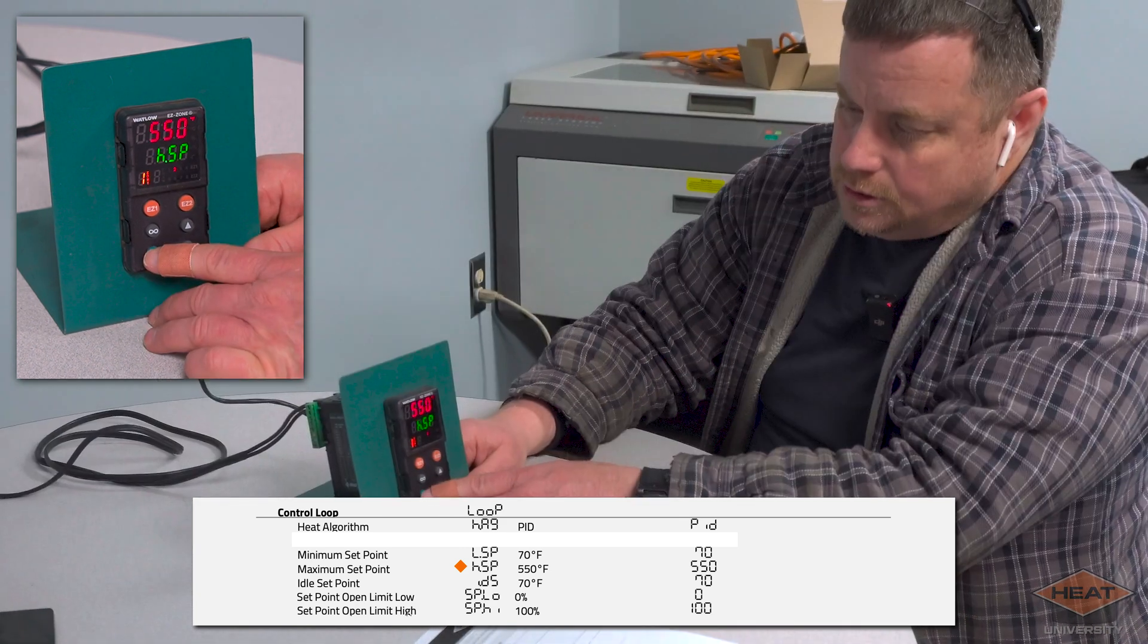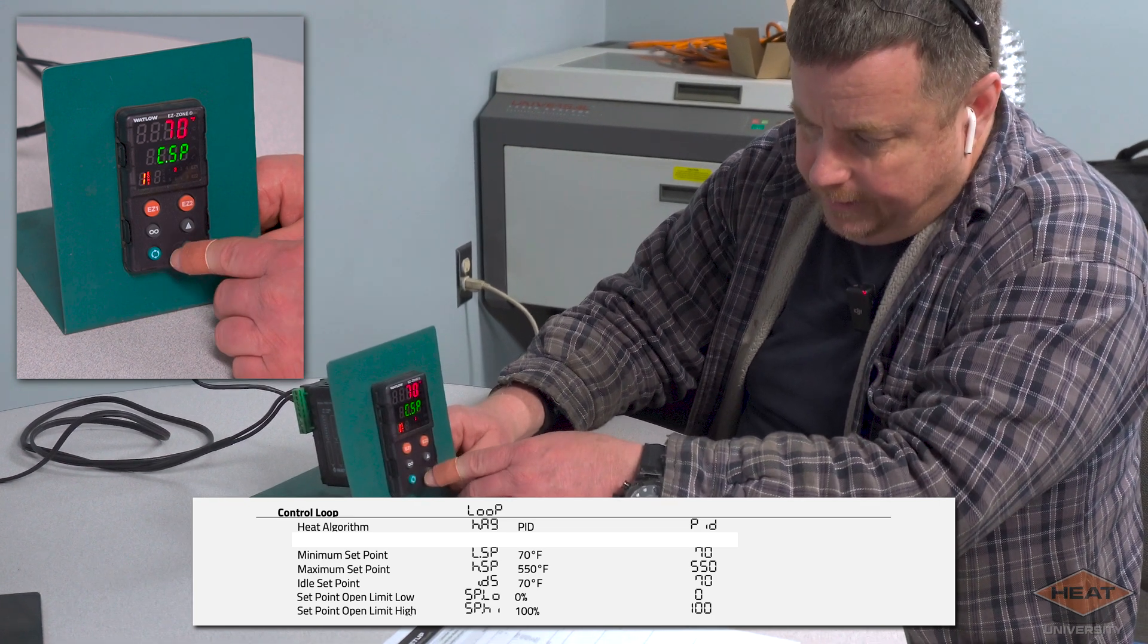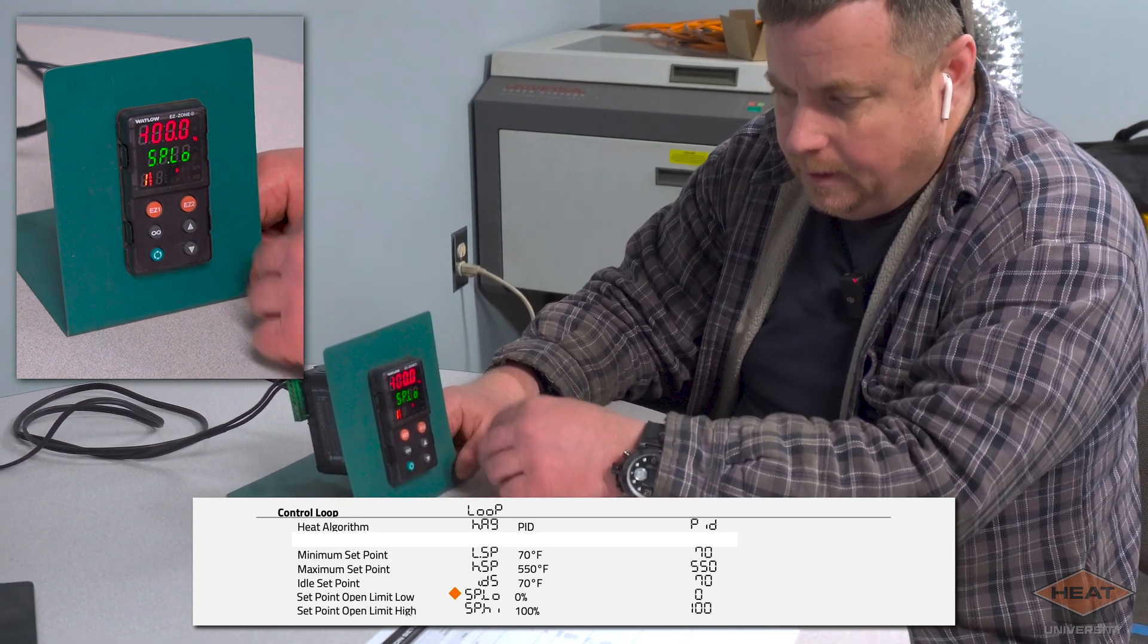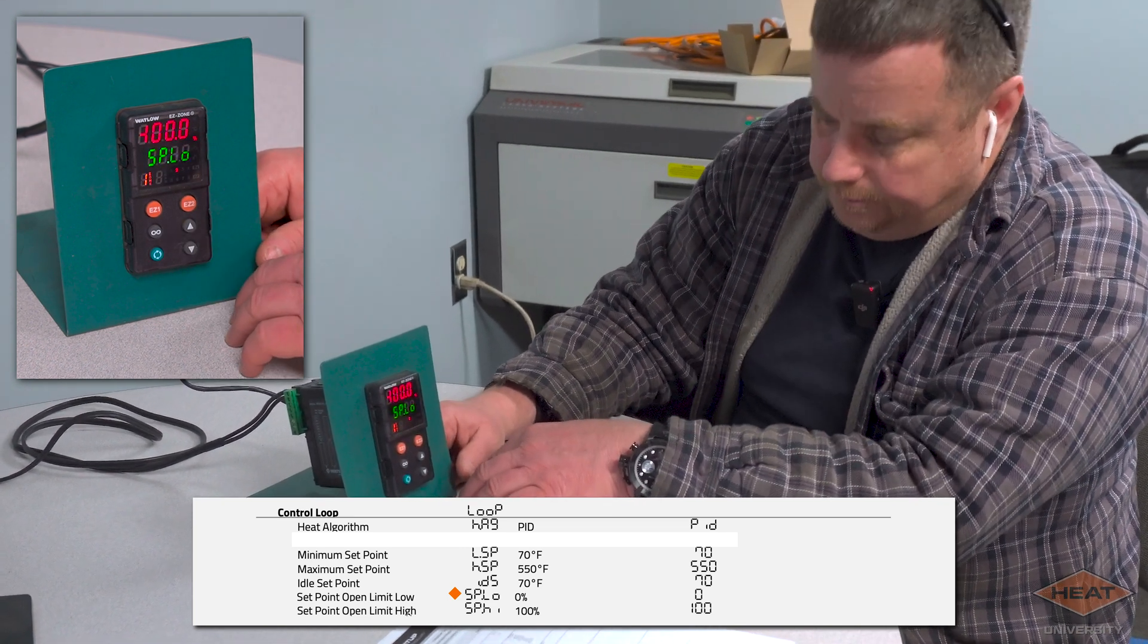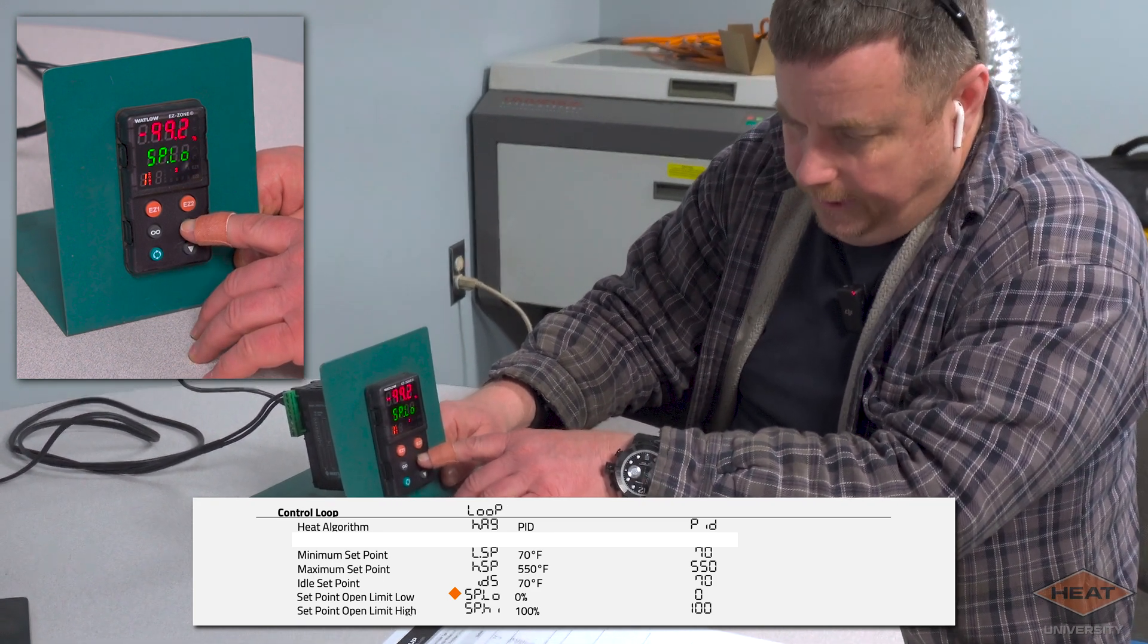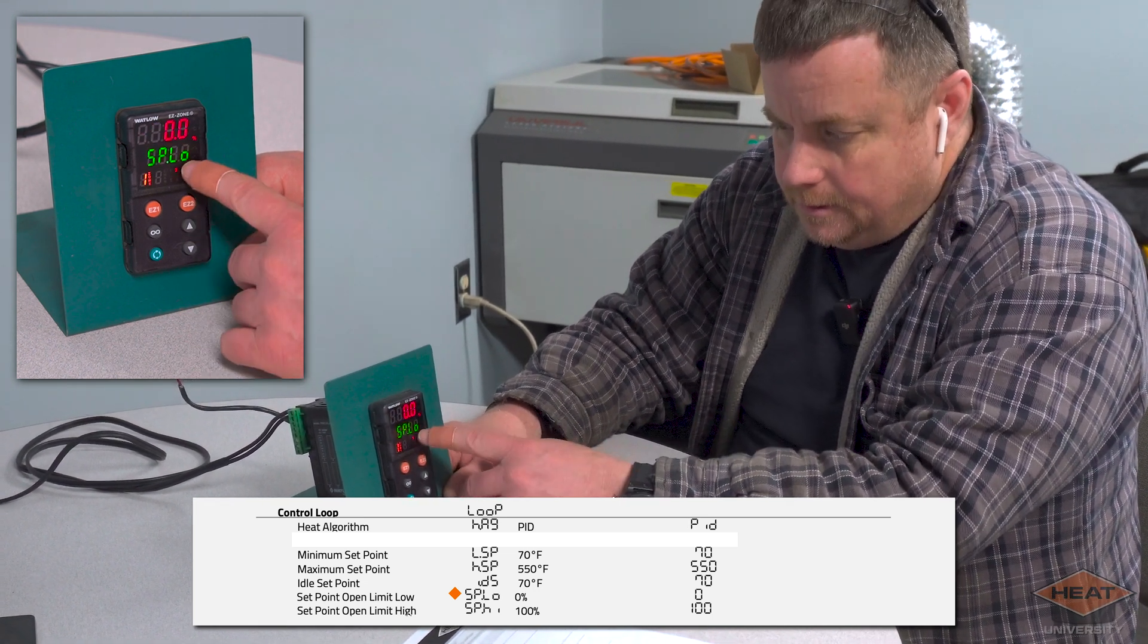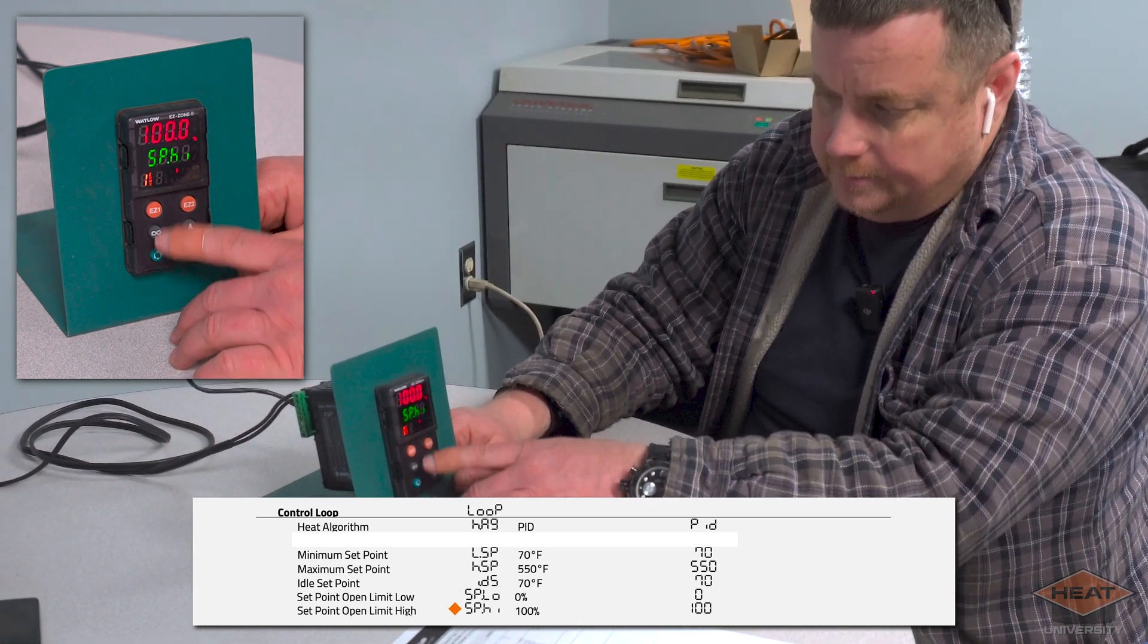So it's 550. We're going to cycle that again. That's our current set point. I usually just make that 70, and then our idle set point I just make 70 as well, just to keep things consistent. Now our set point low, it comes up as minus 100 percent. If this was cooling, we would leave that alone. Since it just has heat, we're going to make this zero. So our set point low is zero, our set point high is 100 percent.